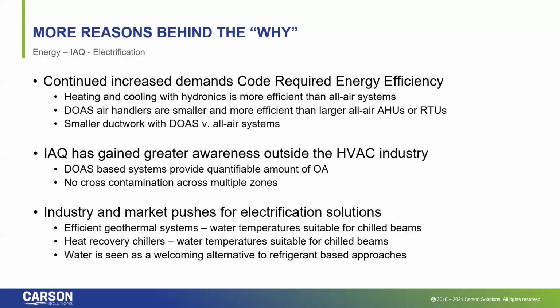Some of the key reasons why I see the opportunity for chill beams being a good fit: first, the continued increase in code-required efficiencies, understanding that heating and cooling with hydronics is much more efficient than an all-air system. DOAS units are smaller than an all-air air handler. Indoor air quality has gained greater awareness within the HVAC industry and general public. And certainly there are industry and market pushes for electrification, where we might start seeing geothermal and heat recovery approaches being a very viable solution.